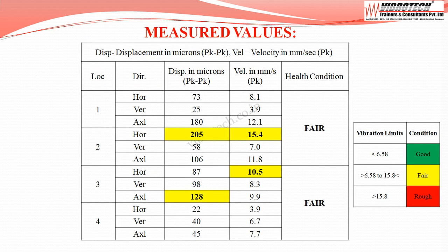The vibration values are maximum at the motor drive end horizontal — velocity up to 15.4 mm/s peak with displacement of 205 microns peak-to-peak — and at the pump drive end horizontal, velocity up to 10.5 mm/s peak and displacement of 128 microns peak-to-peak. The equipment falls under the fair category.